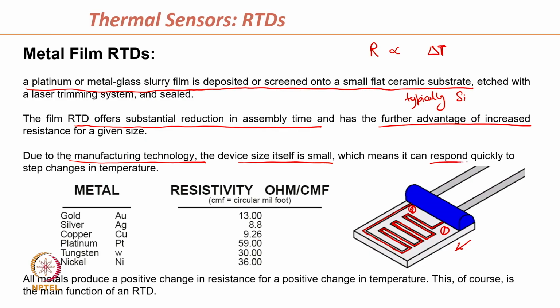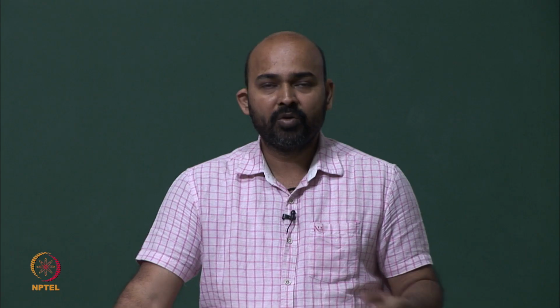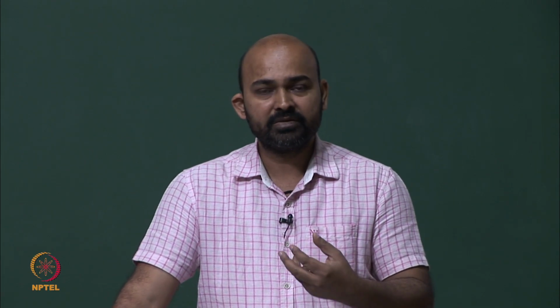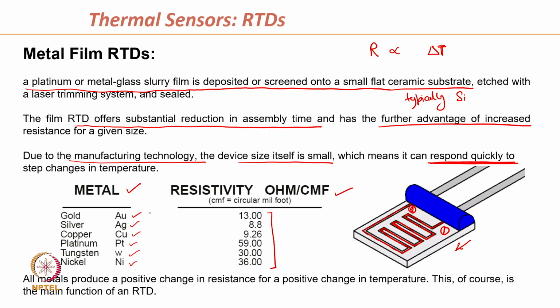So, the response time of RTDs when they are made using thin film is very small. These are some metals and their resistivity in ohm per CMF or the circular mil foot. Let's, for example, we have gold, silver, copper, platinum, tungsten, nickel, and these are their typical resistivities. So, depending upon the application, where we want to have the value of resistance which is fixed by application, we can choose any of the metal from this table.